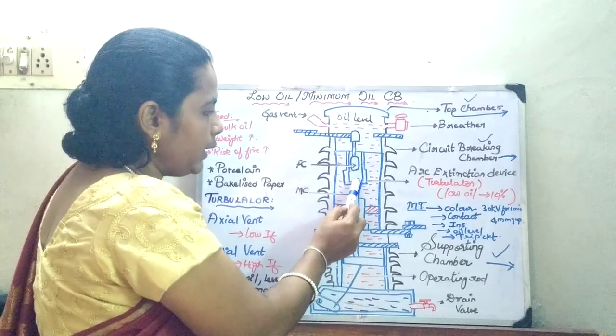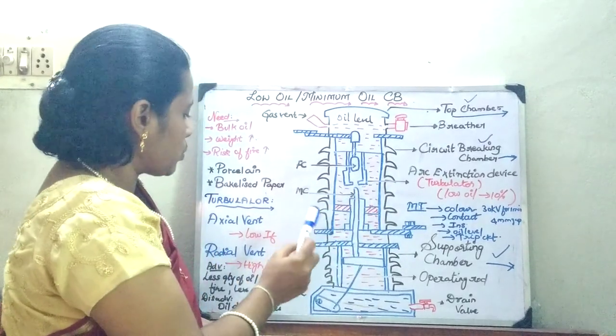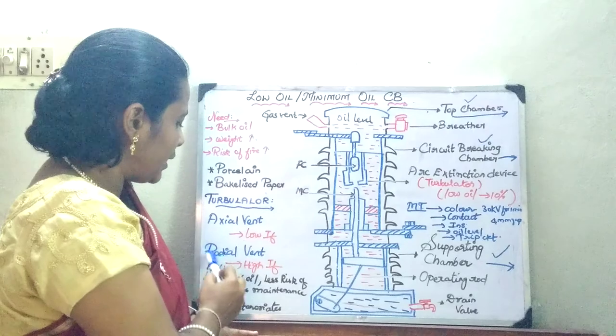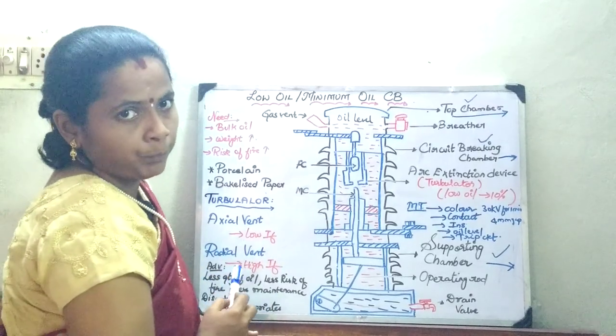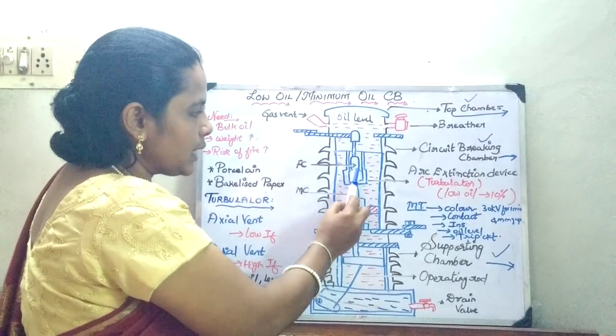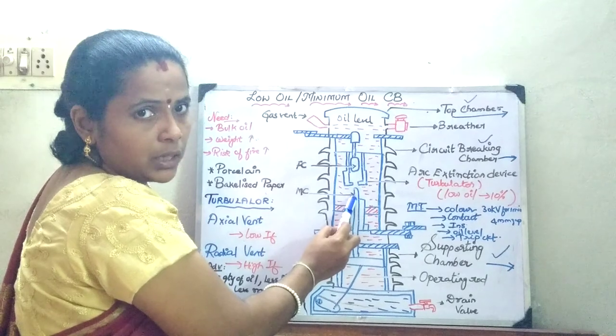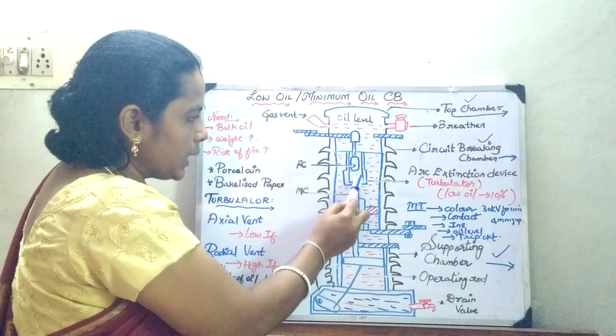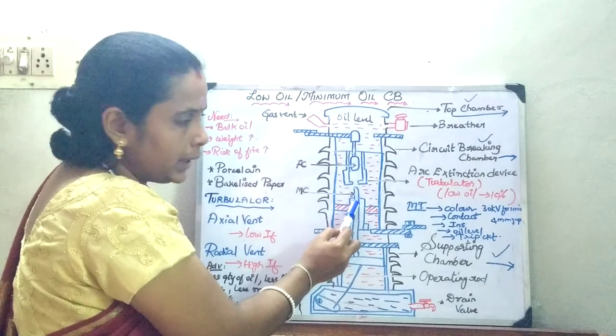So this turbulator is going to have both the vents: axial opening as well as radial opening. So whenever a fault occurs, initially they are going to be stuck with each other. When a fault occurs, arc is going to be struck between the fixed and the moving contact.